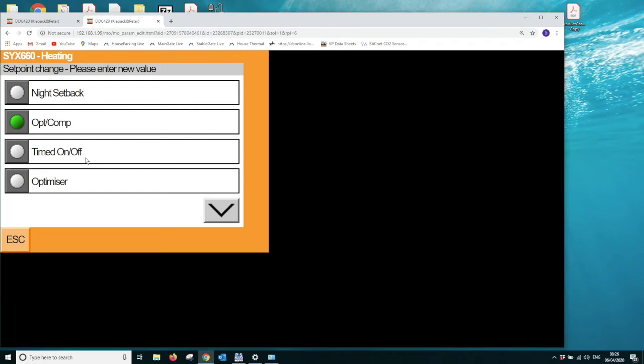frost protection level. This is slightly different to an optimizer compensator, where out of hours we also turn the heating off to frost level, but there is no optimum start with the timed on off. So this is for somewhere where there's a small facility. They don't really want the features of an optimizer. It could become a little bit disruptive for them if plant is starting up out of hours in order to heat the building up. But obviously from an energy performance point of view, an optimizer is always preferred rather than having a fixed time start where you could be overheating a building or even underheating it from a comfort point of view.